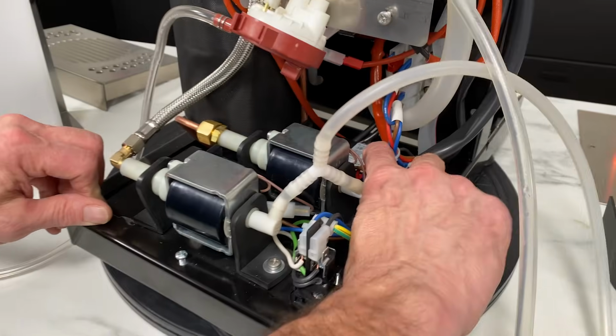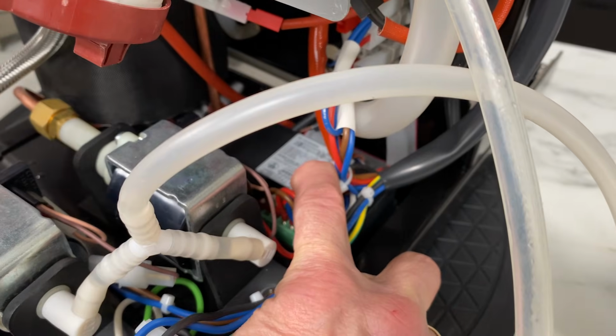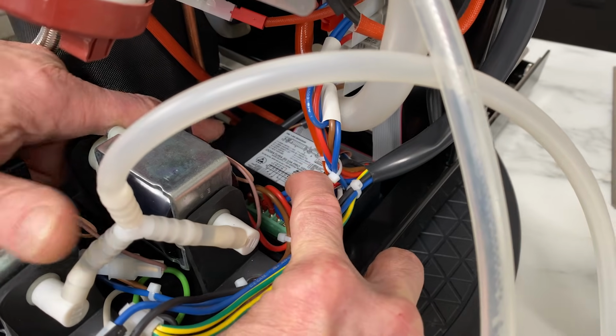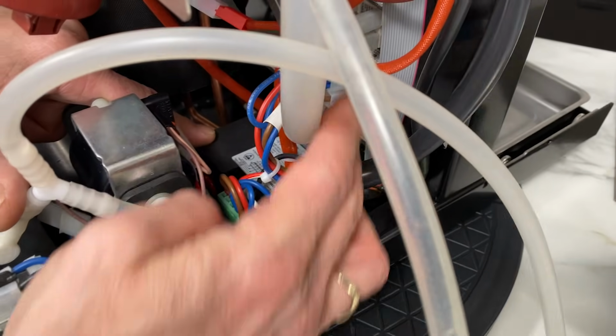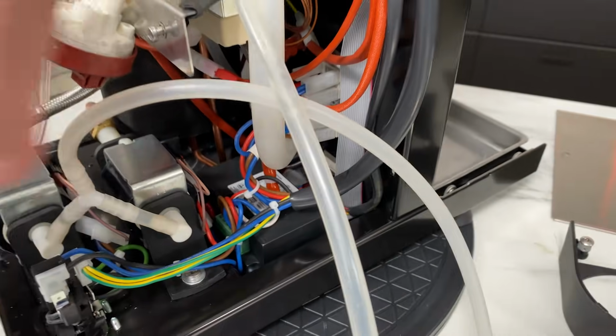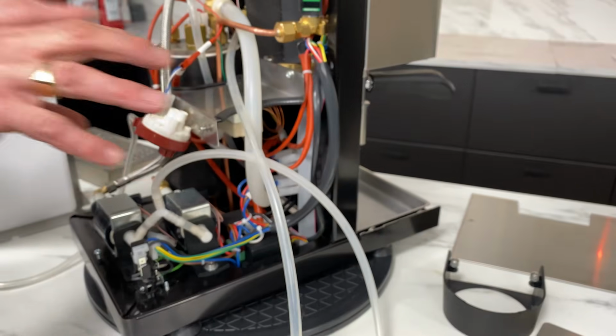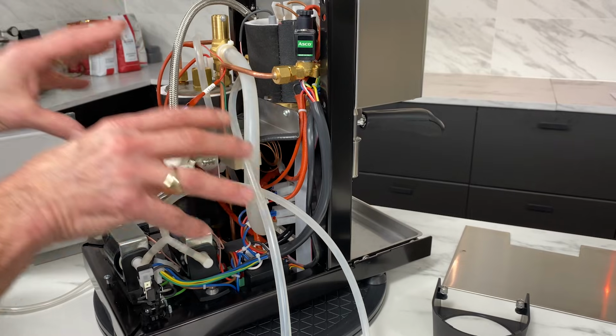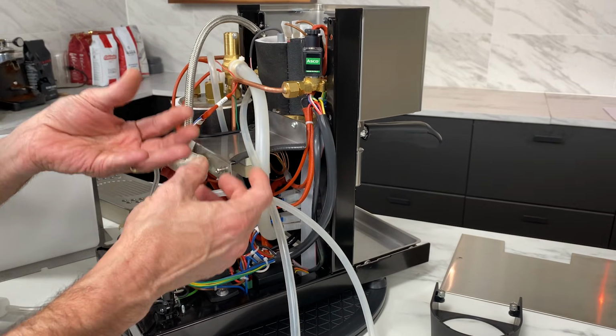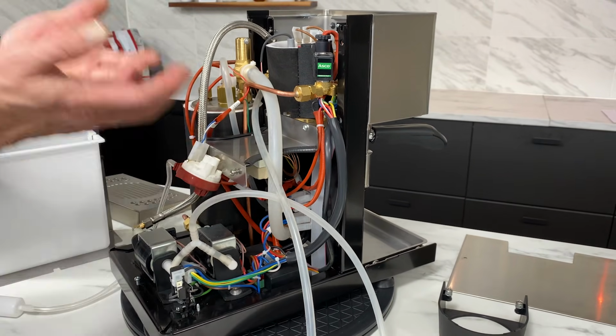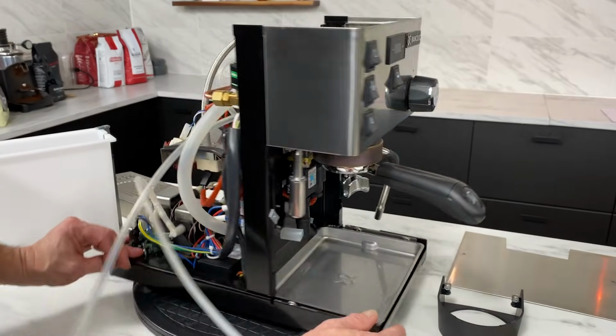Here's a little Gicar controller for the PIDs. Again, both boilers are controlled by PID. So that's down here. We got a couple static relays here. They control power going to the boilers, those short little pulses that are really what makes a PID system work, just little pulses of power once you reach temperature to keep very accurate temperatures.